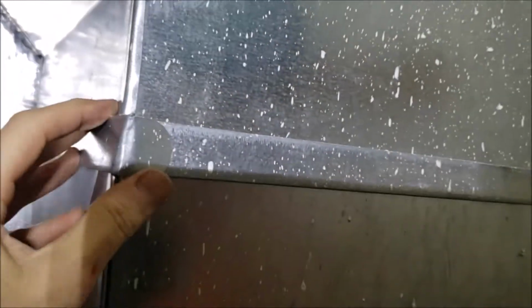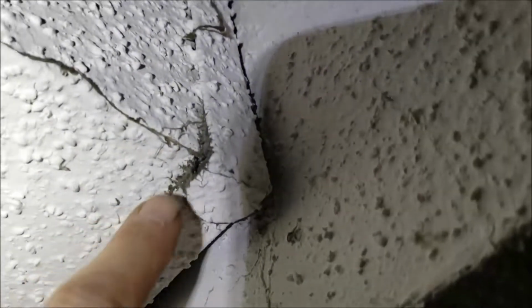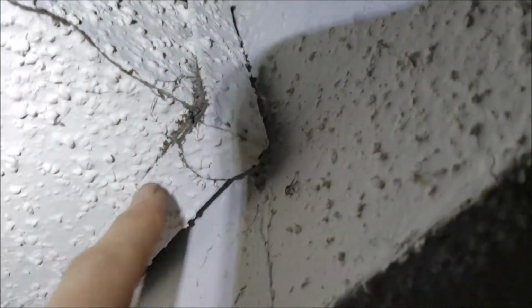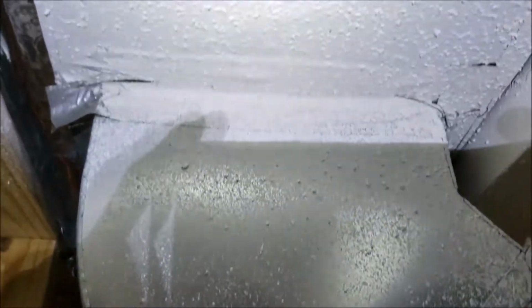In fact, all these joints would be a good candidate for mastic. It's like a putty you brush on there, it dries good and hard, and seals up all those joints. You can see, let me get my light here, how the dust is accumulating and being pulled in there. That's part of the cold air return too, pulling that dust through unfiltered, and it'll work its way right into the air handler up against that radiator and plug it up. So keep those joints all good and tight, keep your system running better and more efficient.